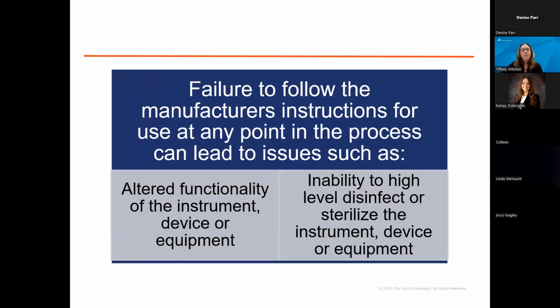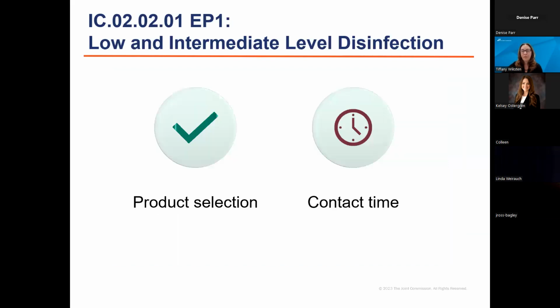So this is just a quick reminder, right? Failure to follow the manufacturer's instructions for use at any point in the process can lead to issues such as altered functionality of the instrument, device, or equipment, which could be a safety event. Not everything is an infection control risk, but it could also result in the inability to high-level disinfect or sterilize the instrument, device, or equipment. That is the infection control issue, right?